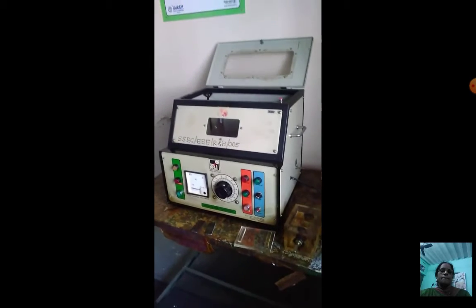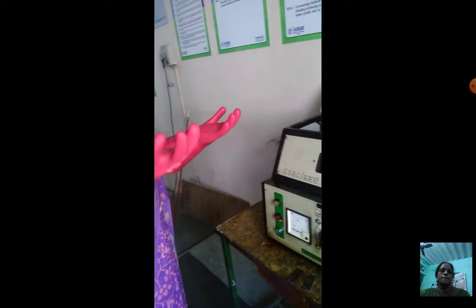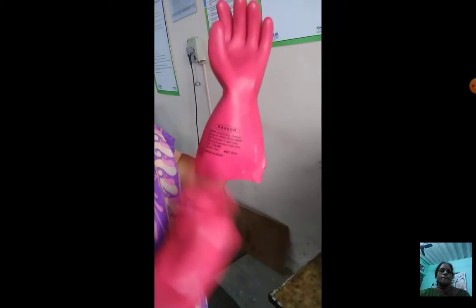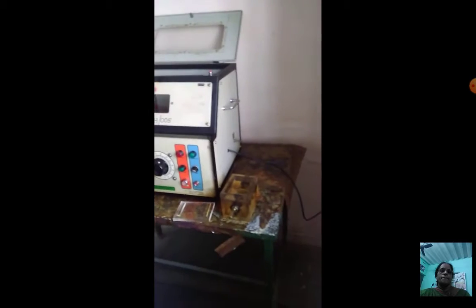And then this is the high voltage transformer. So here this is the primary winding, secondary winding. In between, there is the top bushing. These 2 leads are for fixing the test cell. Before you switch on this test kit, you have to wear rubber gloves. The maximum voltage capable here, you see, is 11 kV only. Then you can properly close it, fixing this test cell. Then you can fix it inside. Now you can close the door.